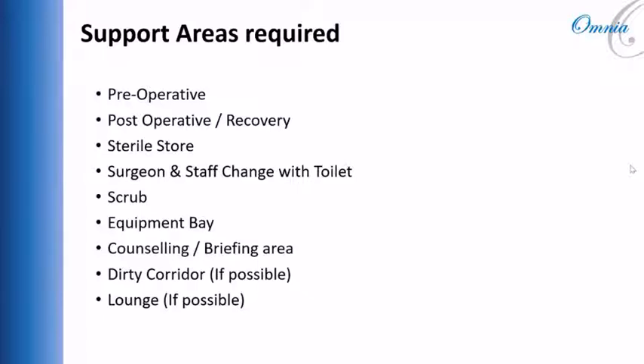We need to have a sterile store which should be directly connected to the CSSD. Surgeon and staff change with toilet. Obviously, this comes out of the sterile zone. It is a non-sterile area. Then scrubs for OT, preferably minimum one scrub for 2 OTs. Then equipment bay, counseling and briefing area. This is a very important area because generally in India, with one patient on the OT table, there are minimum 2 to 3 relatives waiting outside. So you need to brief them, counsel them.